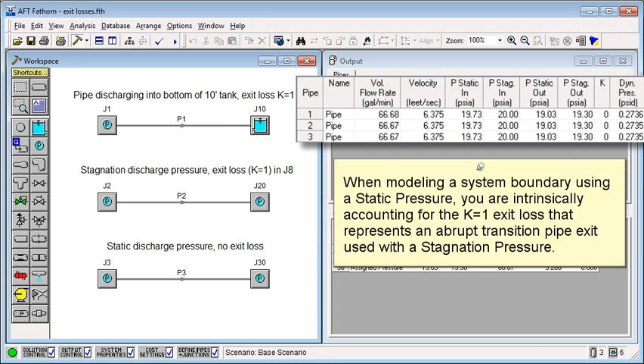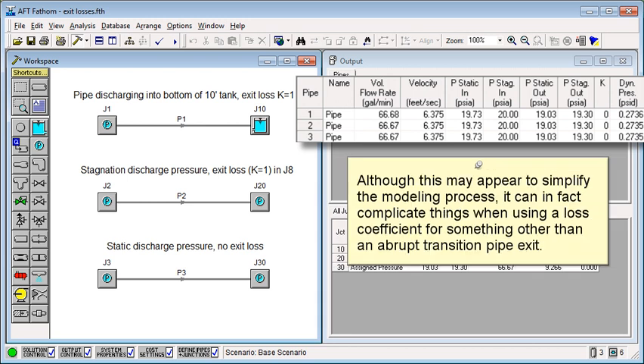When modeling a system boundary using a static pressure, you are intrinsically accounting for the K equals 1 exit loss that represents an abrupt transition pipe exit used with a stagnation pressure. Although this may appear to simplify the modeling process, it can in fact complicate things when using a loss coefficient for something other than an abrupt transition pipe exit.